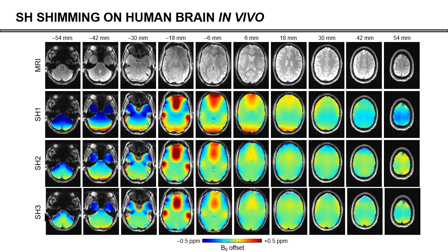This is a typical result — 10 slices of a typical human brain. If you remove the first order inhomogeneity, you can get an inhomogeneity that looks like this: it's not great; ideally it should be perfectly green. There's quite a bit of color everywhere, telling you that the inhomogeneity inside the brain is beyond first order — there are higher order terms in there. If you also remove the second order spherical harmonics, you do improve things, especially on the upper part of the brain it starts to become quite green. But the lower part is still problematic. Even if you remove the third orders, it is still similar, because the air-water boundaries are mostly in the lower slices — right above the nasal cavity — where you have the strongest inhomogeneity. Most MR scanners only have up to second order, so this is basically the best shim you can do.